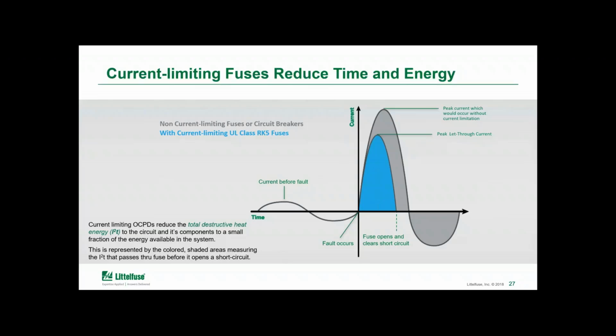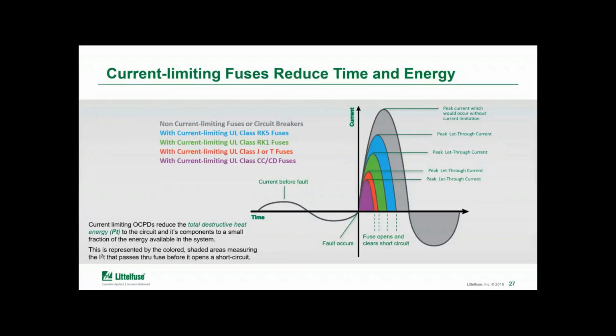Now, the slide here, the gray area under the curve, would represent all the energy released when there's a fault and you're not using any current limiting devices. So in this case, when a current limiting fuse is used, we're showing a class RK5 as the first curve. With that class RK5 design, the fuse clears the circuit before the first half cycle, and that will dramatically reduce the amount of total energy that's dissipated. I also put on the RK1 fuse curve, and you can see by comparison, it's also a current limiting fuse, but has a smaller area under the curve and therefore less energy let through. Class J or T fuses are even more current limiting, and CC and CD are even more current limiting beyond that. So looking at the fuses you're using in the facility can have an impact as well.